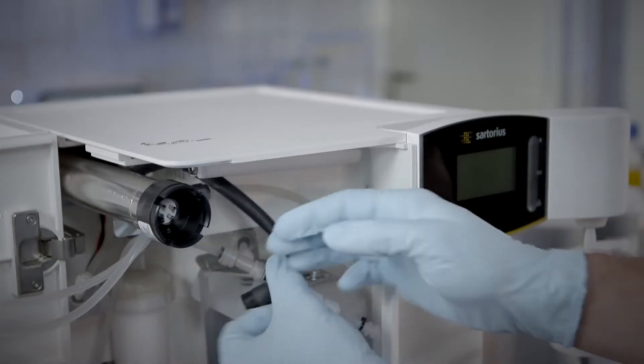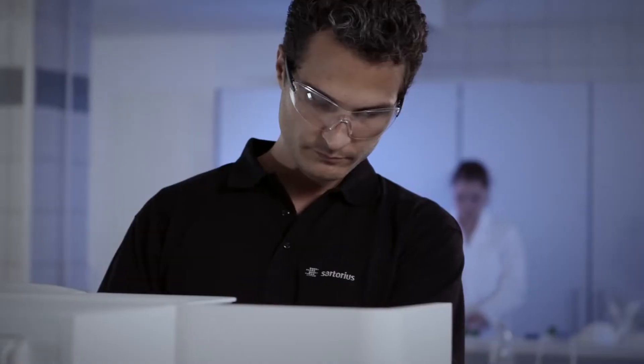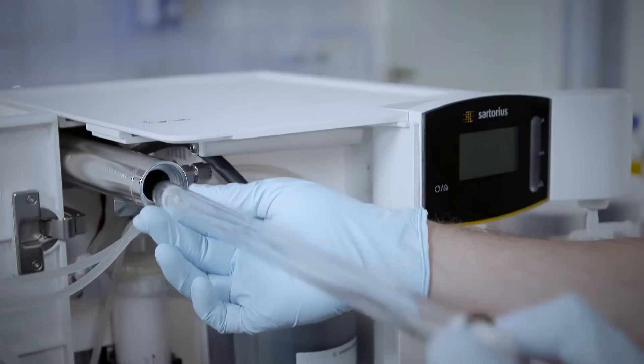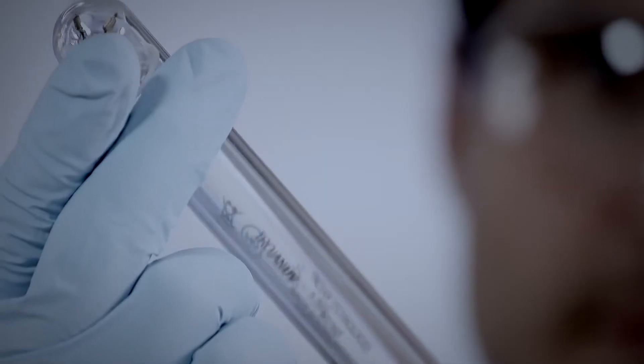Horizontally built in, the UV lamp with wavelengths of 185 and 254 nanometers offers outstanding efficiency. Contrary to vertical units, the temperature gradient is less developed and enables a reduction of organic components to less than or equal to 2 parts per billion.